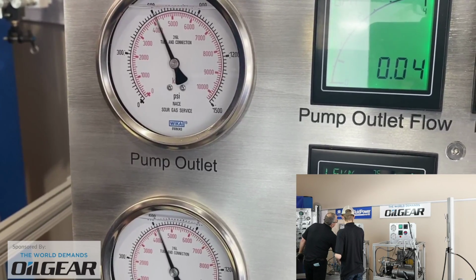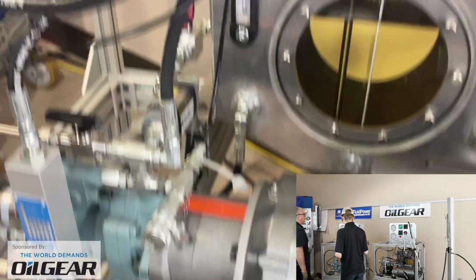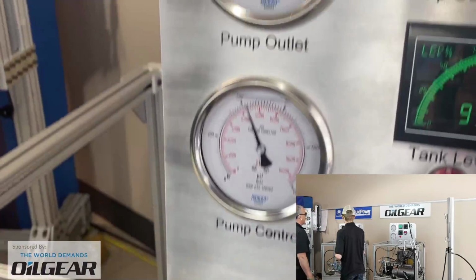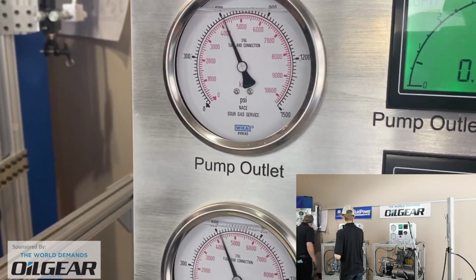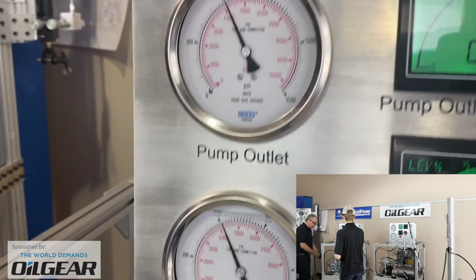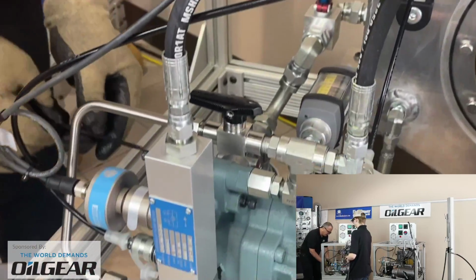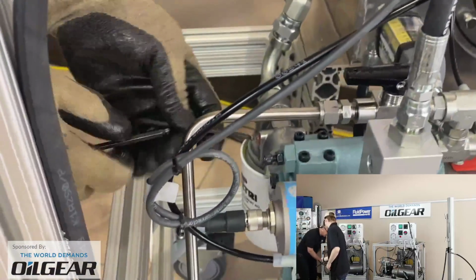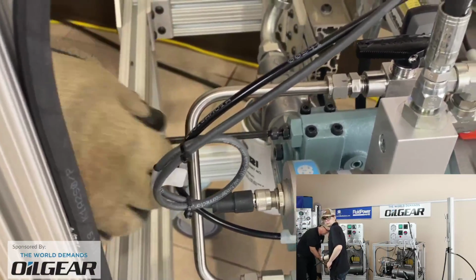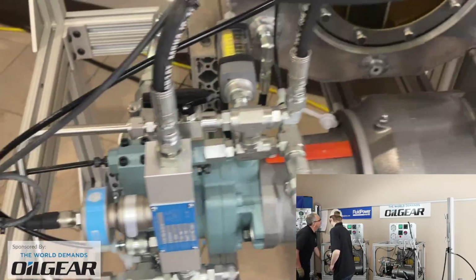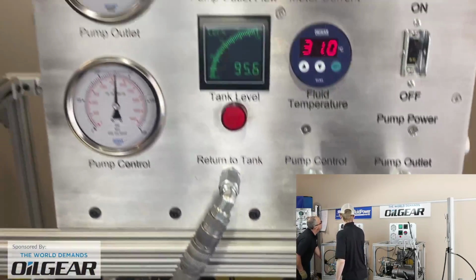As our flow rate drops off to 0, we find out that our pressure compensate at the moment is around 600. Perhaps our pressure compensator is supposed to be closer to 750. So just got to grab the right key and dial into our pressure. Always check your manuals to find out where your pressure compensator is located.